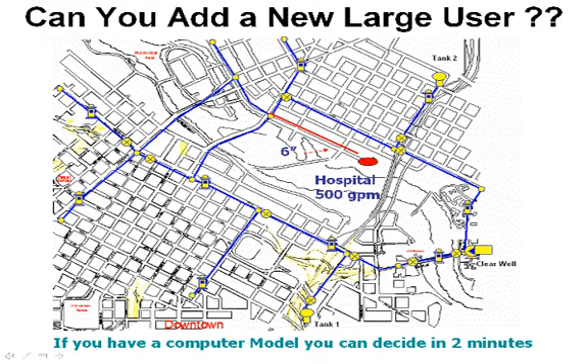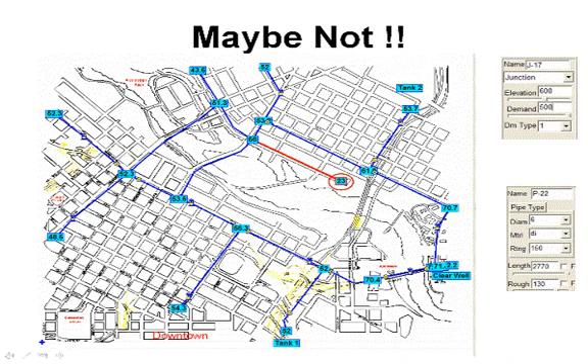We asked earlier: can you add a new user here? We can very quickly add a pipe and a demand — it only takes seconds to evaluate this. In fact, here we see the pressure is only 23 PSI, so we can't add a new user with a 6-inch pipe. If we do an 8-inch pipe, we could quickly evaluate whether that would do the job.